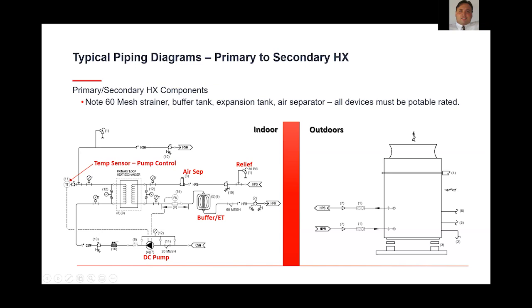You'll also have flow sensing requirements, typically with a fairly high degree of precision in order to activate and cycle on typically a direct commutated variable speed pump on that secondary side. So I kind of talked about that before. Because of the high degree of flow turn down and modulation, you're dealing with direct commutated pumps in most cases, potable rated. You have to have a control means of triggering that. You have to have temperature controls in this in order to maintain and hit that discharge water temp target. So again, this is your primary side between the heat pump, a secondary heat exchanger, and then this would be your cold water supply down here at the bottom coming from your storage tanks, that cold tank that I mentioned before, and then hot water supply being generated going to that hot tank.